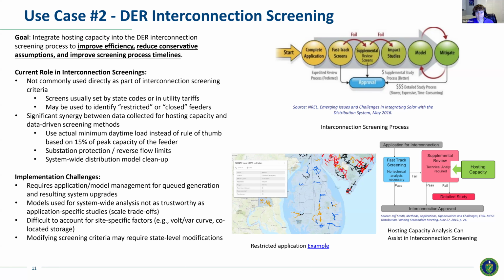Implementation challenges holding this back from wider adoption: you have to be able to effectively model queued generation in the power flow and hosting capacity, which can be tricky and changes if, for example, projects pull out of the queue - it can upset the modeling process quite a bit. It's a system-wide analysis, so it may not be as trustworthy as something an engineer spent a lot of time poring over, and it can be difficult to account for site-specific factors. Generally, hosting capacity doesn't consider volt-var curves for new generation, co-located storage, and other factors that may impact actual performance. In some cases the screening criteria are built into state admin codes, so it's hard to change them, and it becomes cumbersome to inject more technical stuff in there.